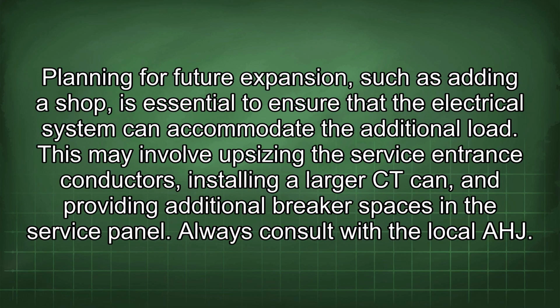Planning for future expansion, such as adding a shop, is essential to ensure that the electrical system can accommodate the additional load. This may involve upsizing the service entrance conductors, installing a larger CT can, and providing additional breaker spaces in the service panel. Always consult with the local AHJ.